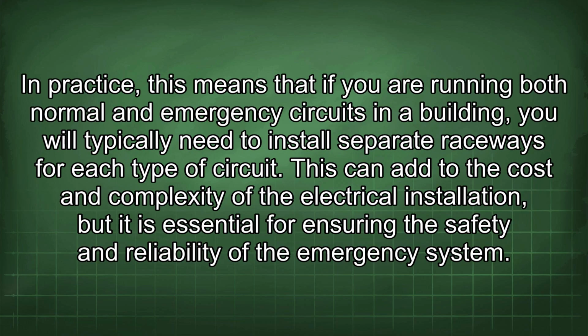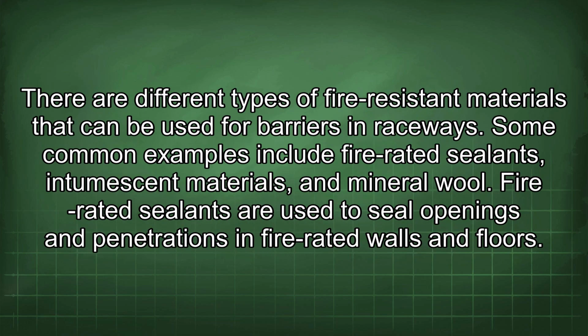In practice, this means that if you are running both normal and emergency circuits in a building, you will typically need to install separate raceways for each type of circuit. This can add to the cost and complexity of the electrical installation, but it is essential for ensuring the safety and reliability of the emergency system. There are different types of fire-resistant materials that can be used for barriers in raceways. Some common examples include fire-rated sealants, intumescent materials, and mineral wool.